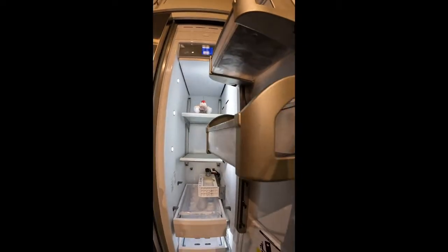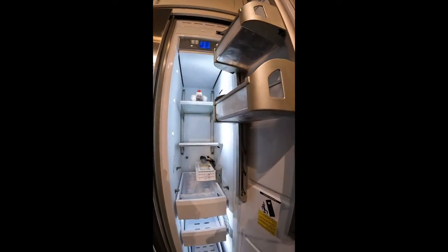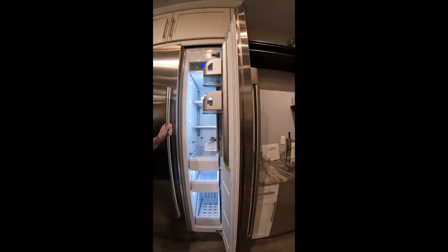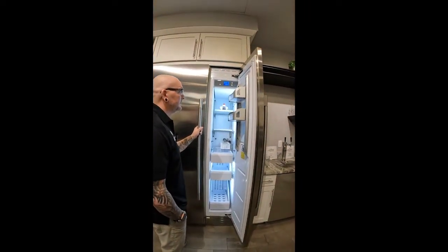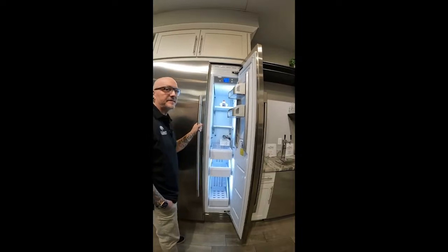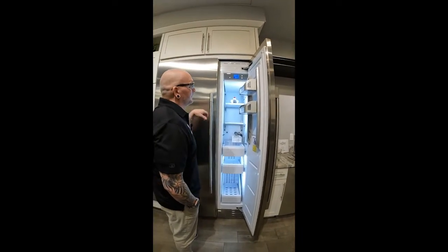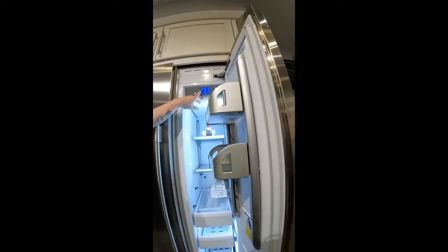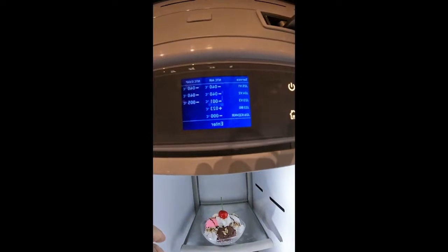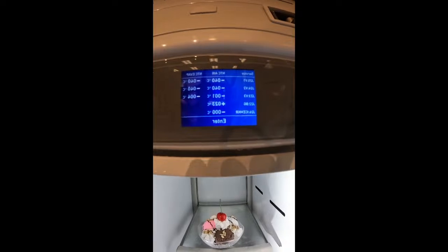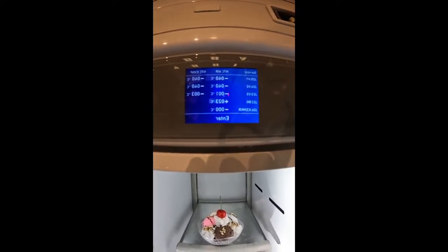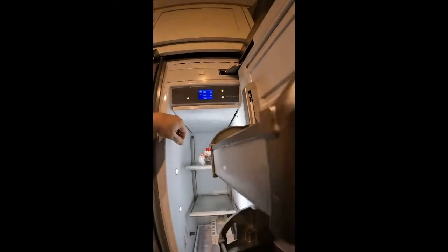So this is a great tool, a great resource for us technicians to know what's really going on inside that machine, real-time temperature sensor. So if the ice maker sensor was way out of range or reading -40, we know that -40 is an open sensor. It's just a bad sensor right off the bat. So going back to the V1, V2, see how it says -40? Again, this is a freezer column. You do not have an air and evap sensor on this freezer column, so it's reading -40, an open sensor. So if you're in the field and you're on a combi unit that has a fridge and a freezer, and you see -40 in one of those places, that's a bad sensor.